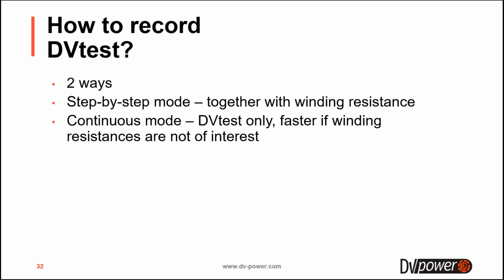So if you remember from the beginning, we said that DVtest is injecting a DC current through the winding, through the OLTC, and recording that current when the tap changer operates. And of course, the winding resistance is measured in a similar way. You inject a DC current through the winding, you measure the voltage drop and the current, and then you calculate the resistance. So this means you can do winding resistance and DVtest together.